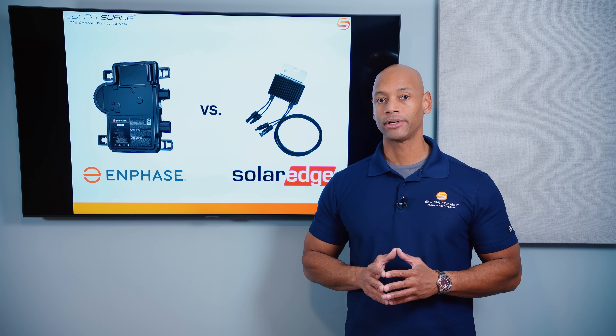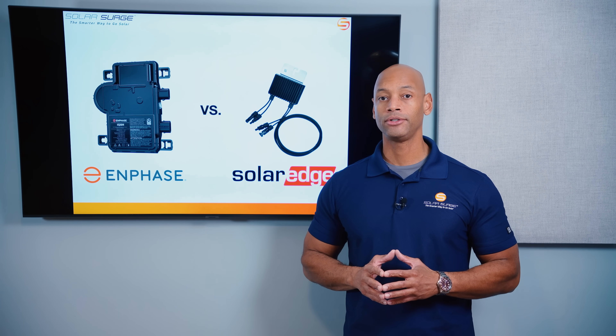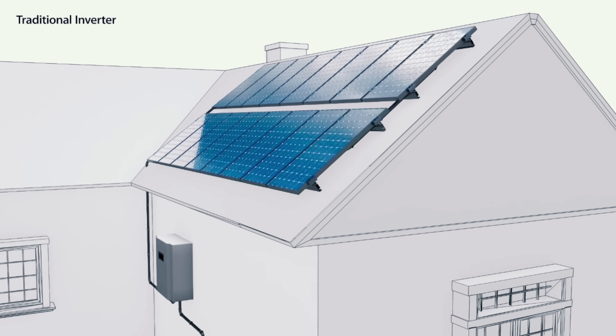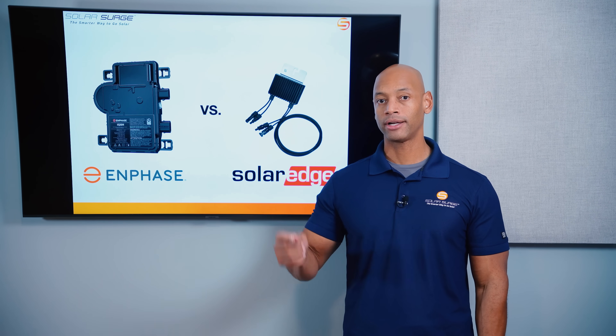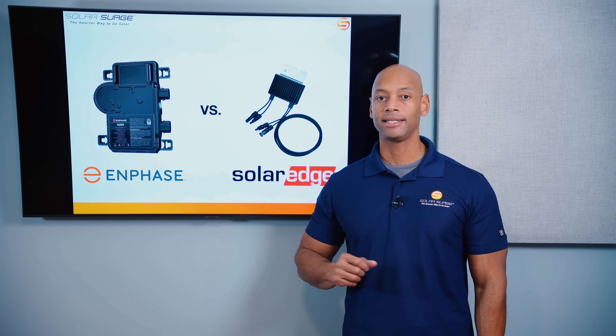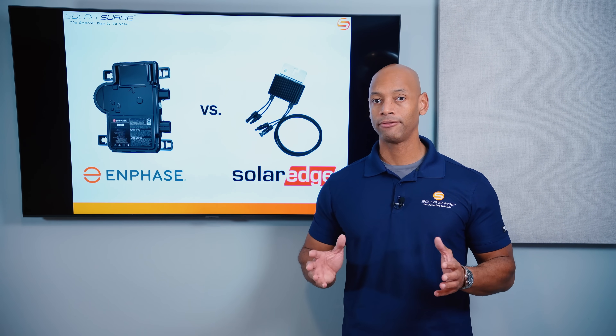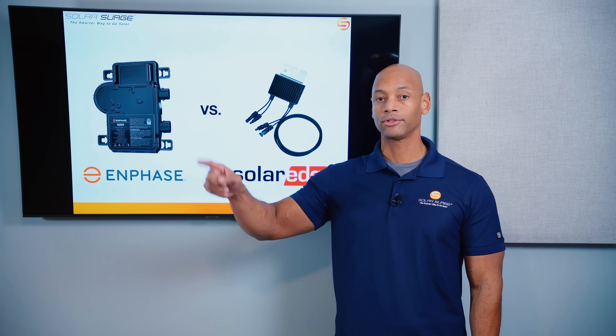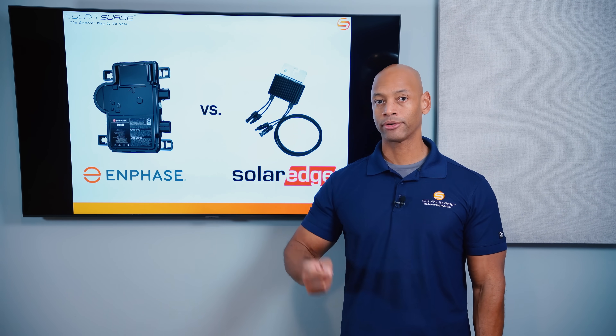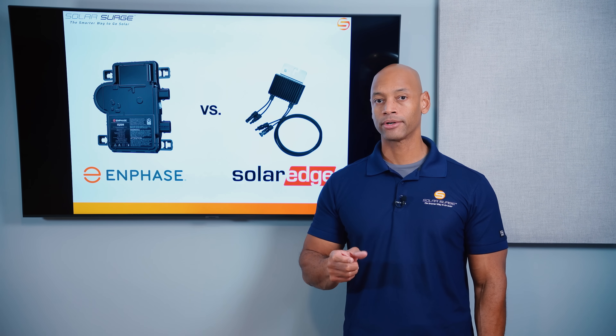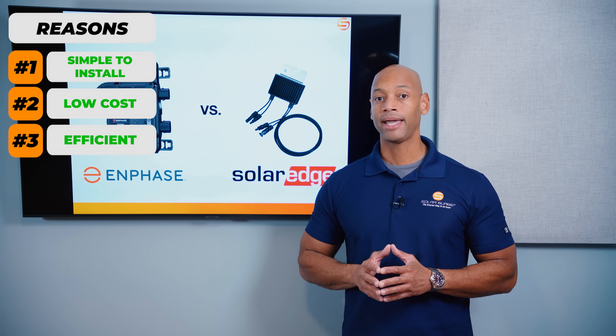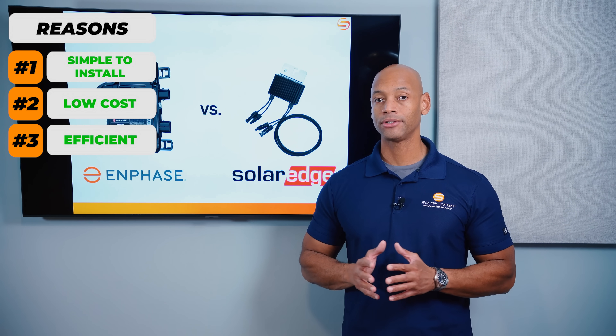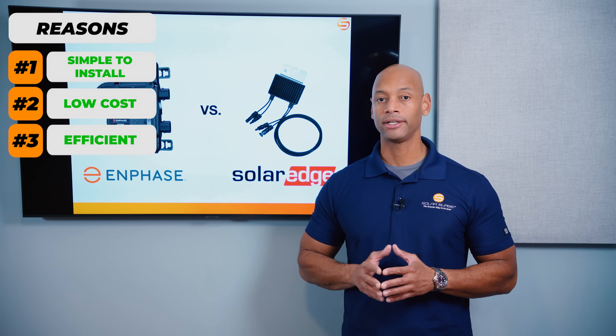Back in the day, prior to 2012 or so, pretty much all solar being installed on US homes used a central inverter or string inverter. The solar panels were wired together in series strings, typically 8 to 12 solar panels at a time, and that string was brought down to an inverter at ground level for DC to AC power conversion. This architecture worked great — simple wiring on the roof, a small conduit down to ground level, relatively low cost, and mostly efficient, as long as you didn't have any shading issues.